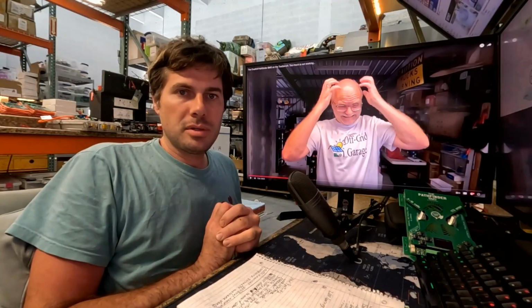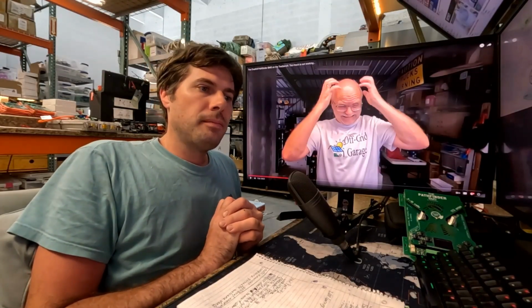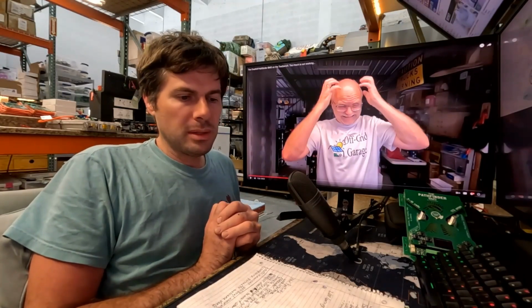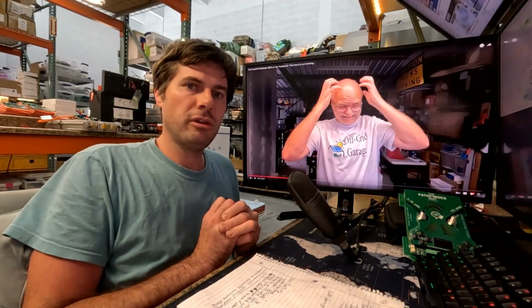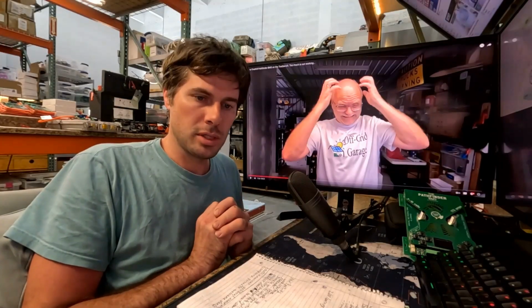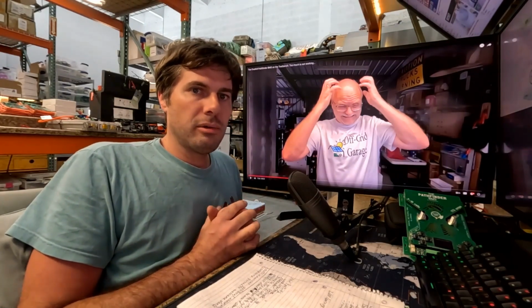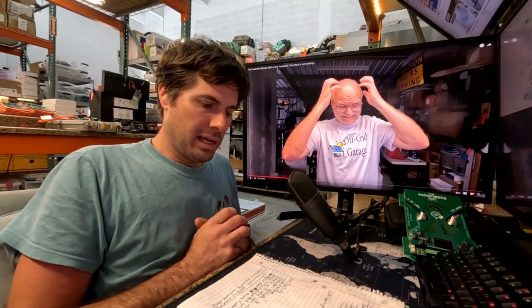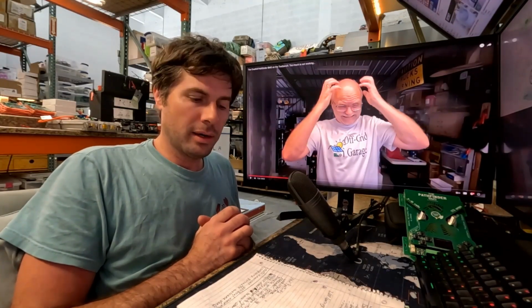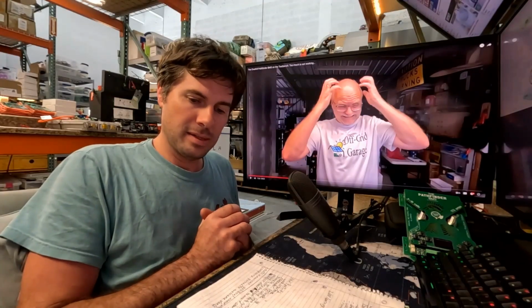Presently it was set at 12 milliamps, which I'll admit now is too low. 12 milliamps is really within the noise floor of the current sensor. So I think I'm going to change it to 50 milliamps, and below 50 it'll just always say 0. That's normal in analog circuits to have a deadband around 0, because it's going to drift a little bit with temperature and time, so it's normal to have a deadband where it only shows 0.